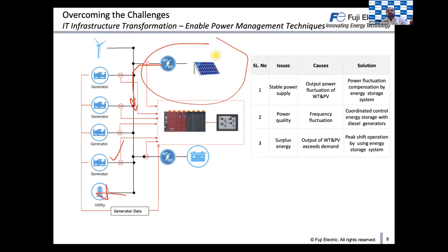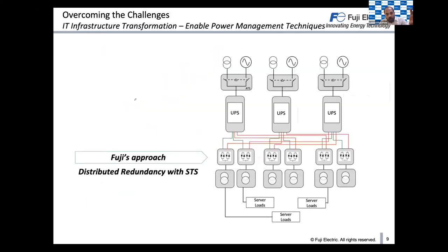And the second thing, we try to incorporate sustainable development into my infrastructure so that I can use different power management techniques. I can use a VFD drive. I can use solar generation. I can use energy storage systems for effective power management. Or we can use a different topology of construction or design, the multiple N configurations, where you can reduce the number of UPS systems in your infrastructure with the help of these ATS. We go for a distributed redundancy so that the UPS efficiency can also be improved with the right infrastructure and the right power management techniques.